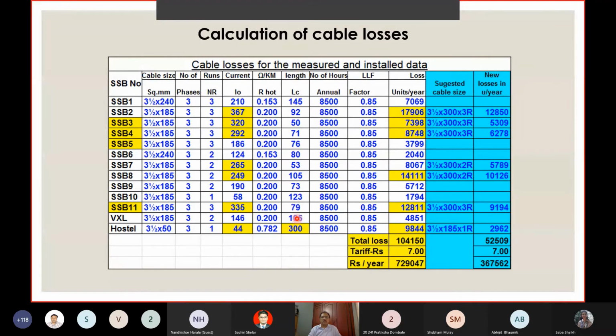We cannot measure the resistance at site because of the length involved and other interferences. So we take it from the catalog. The length we also find out from the customer. Then the number of hours of operation in which the cable is switched on. And a loss load factor we assume as 0.85. And we work out the losses in each of the feeders. So this is that 1 to 6% loss. If you recollect the slide which I showed you, the distribution losses are 1 to 6%.